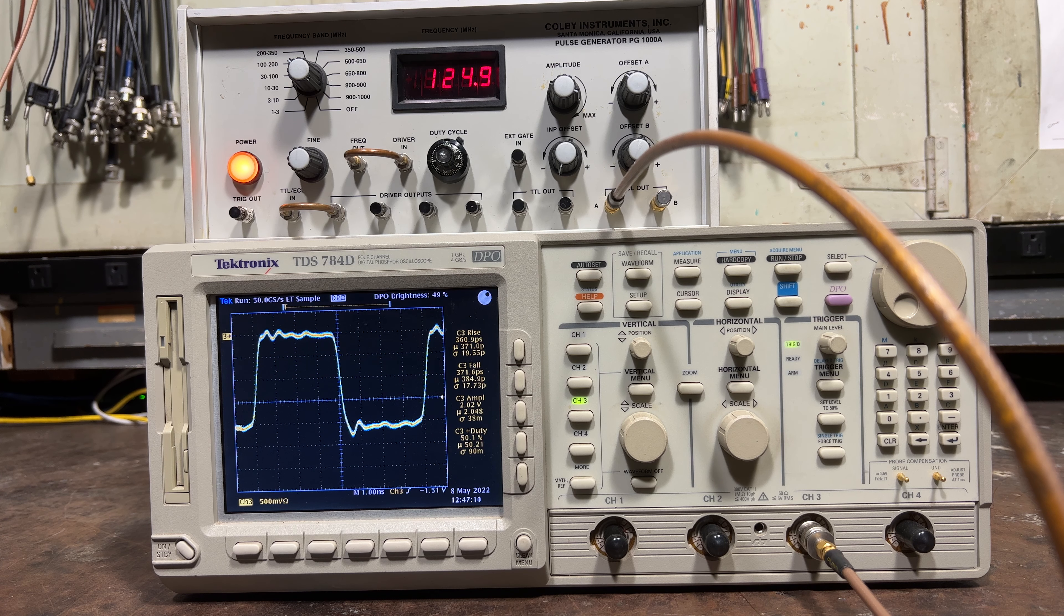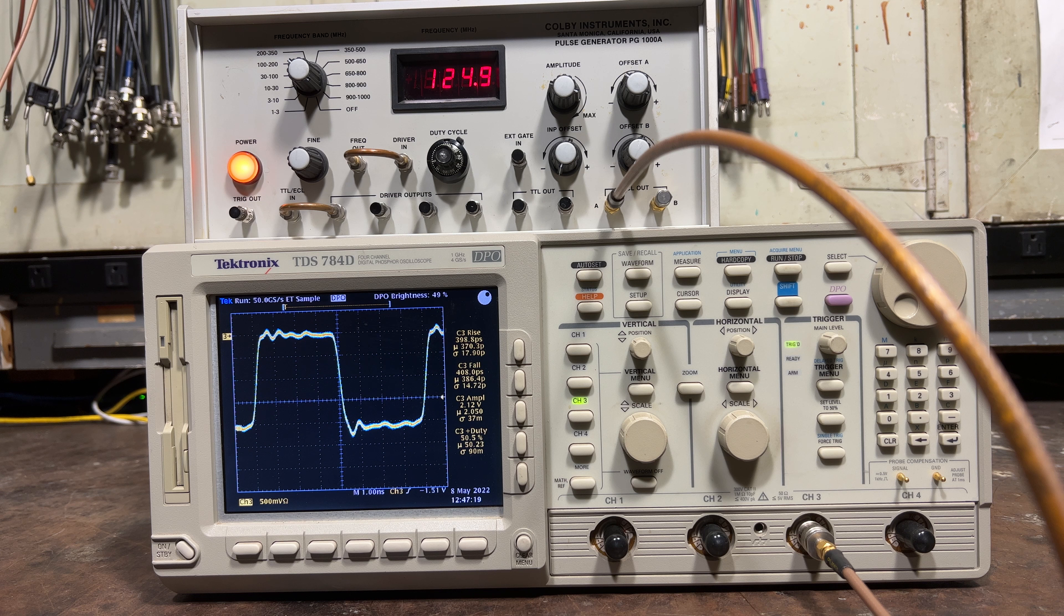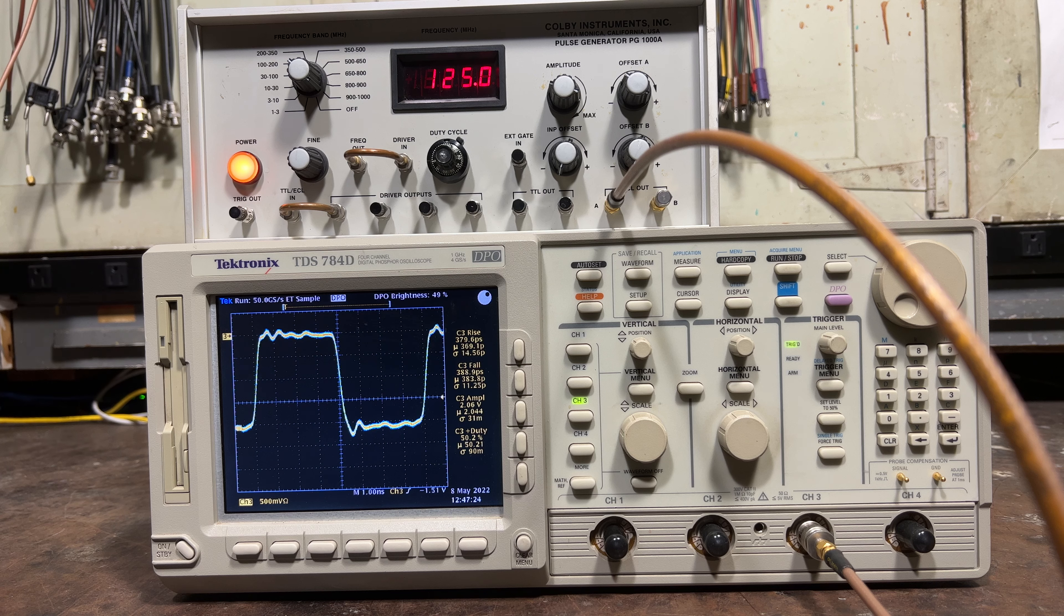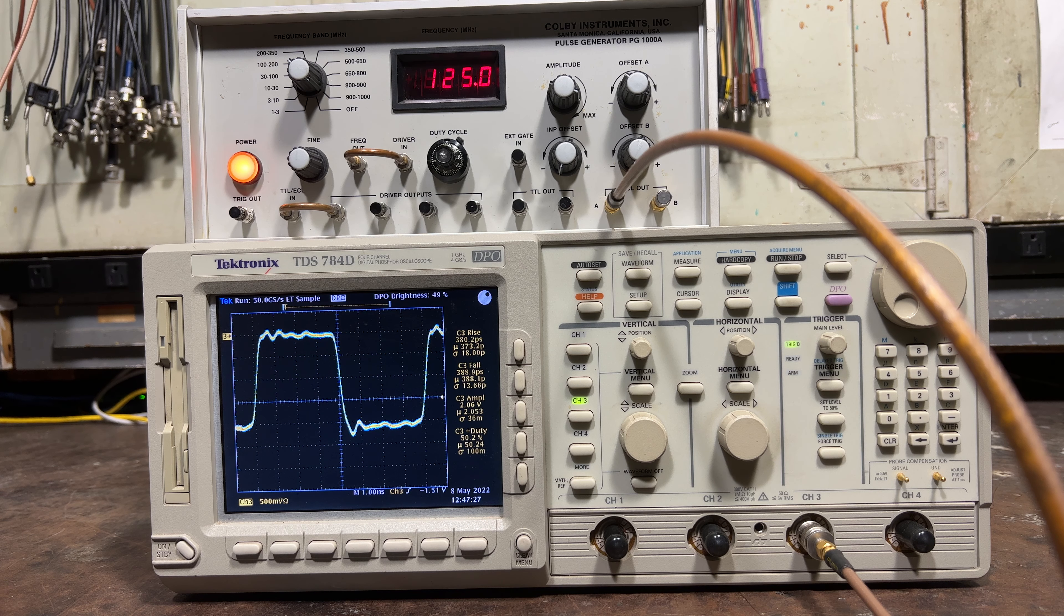Here to show the rise and fall time measurement limitations of the Tektronix TDS-784D, I'm using my Colby Pulse Generator to put out a 125 MHz square wave directly into the scope. The rise and fall time of the generator is on the order of 200 to 250 picoseconds.